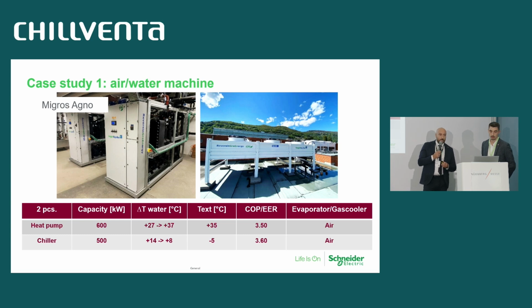Now let's go into detail to the first installations we made. The first of all was Migros Agno, a medium-large shopping mall in the Italian part of Switzerland, close to Lugano, when we installed 2 identical reversible air-water heat pumps. In this brief chart, I highlighted the water temperature level. So, for example, in this existing shopping mall, we produce for space heating water up to 37 degrees, and we cool it down during air conditioning operation to 8 degrees.